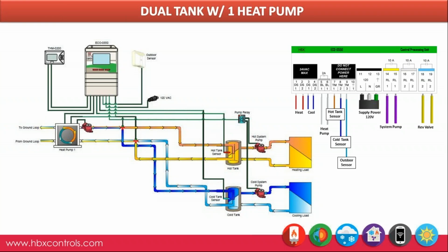In terms of wiring, here is how you would wire up a dual tank heat pump. You would wire heating or cooling demands from your thermostat. It doesn't have to be an HBX thermostat; this control is universally compatible with any thermostat on the market. Your first stage would be pins 5 and 6 for your heat pump, and then 7 to 10 is where you hook up your hot tank, cold tank, and outdoor sensor. Pin 10 is your common for all these 3 sensors, so make sure the second wire of all these sensors is wired into pin 10 to act as your common.